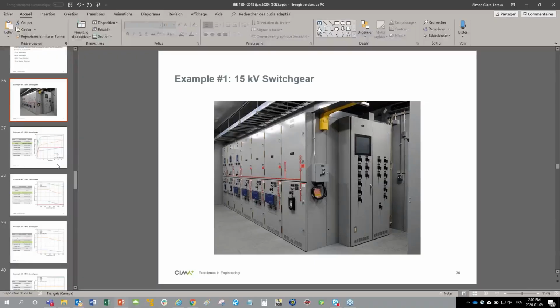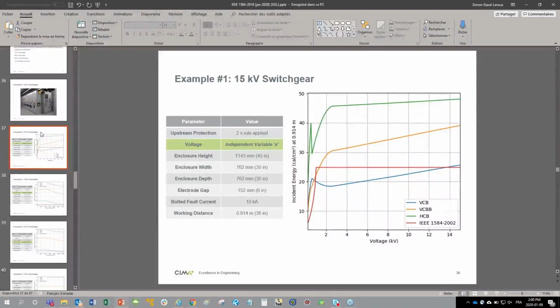All right. This is a question from Barry. He says, example 1 stated that the 2-second rule should always be applied at the utility incoming location due to relay times possibly changing at the serving utility. Is the 2-second time to be used on utility incoming location when below 15 kV? For example, at a 600 volt switchgear location?